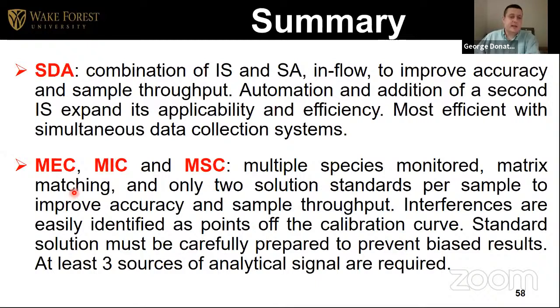It is also matrix matching. You only need two standard solutions, just like SDA per sample. So you can improve accuracy and sample throughput compared to SA, for example. Another interesting thing, you can look at the calibration curve. If any point is off the calibration curve, that is an indication of a spectral interference, which you couldn't do with a traditional method. So any point off the curve will indicate a spectral interference, not matrix interference. So it can be used that way.